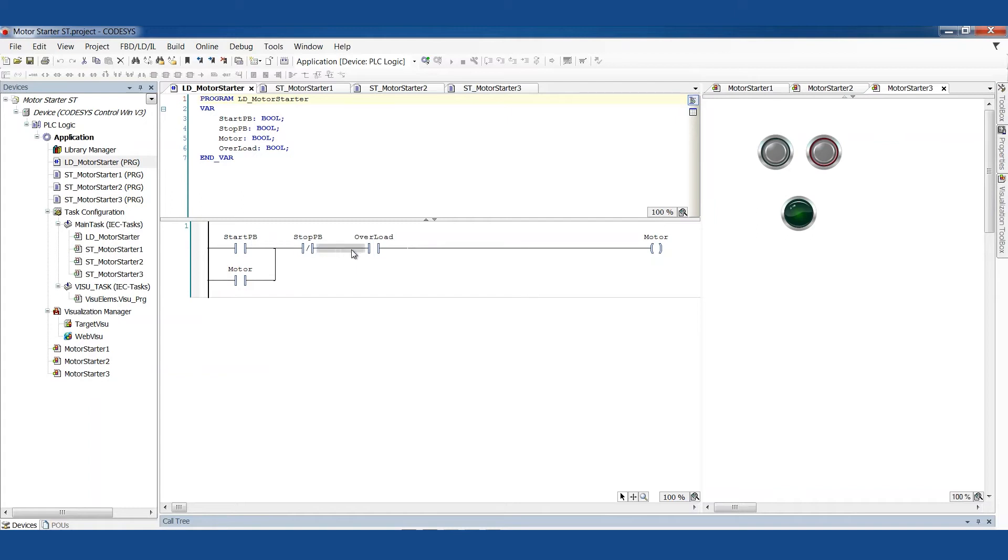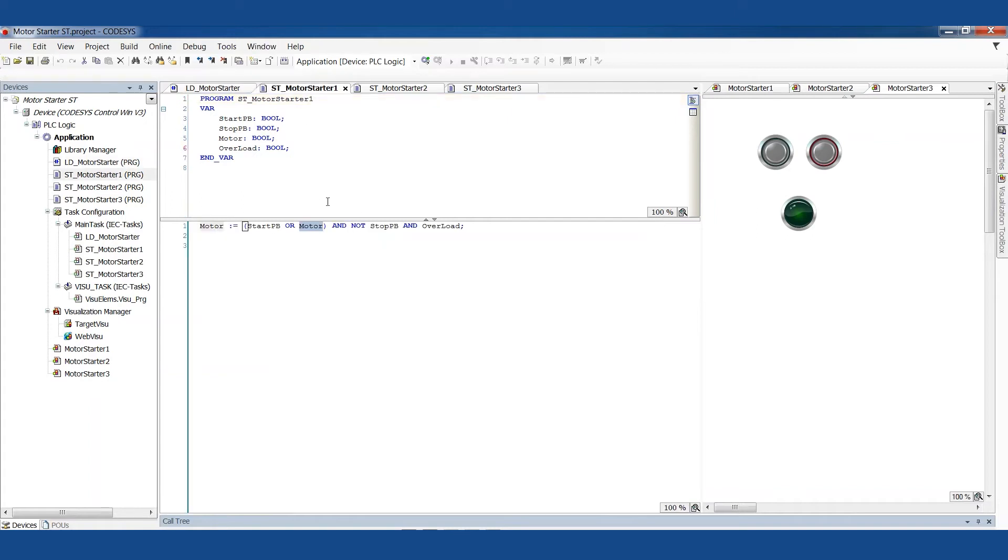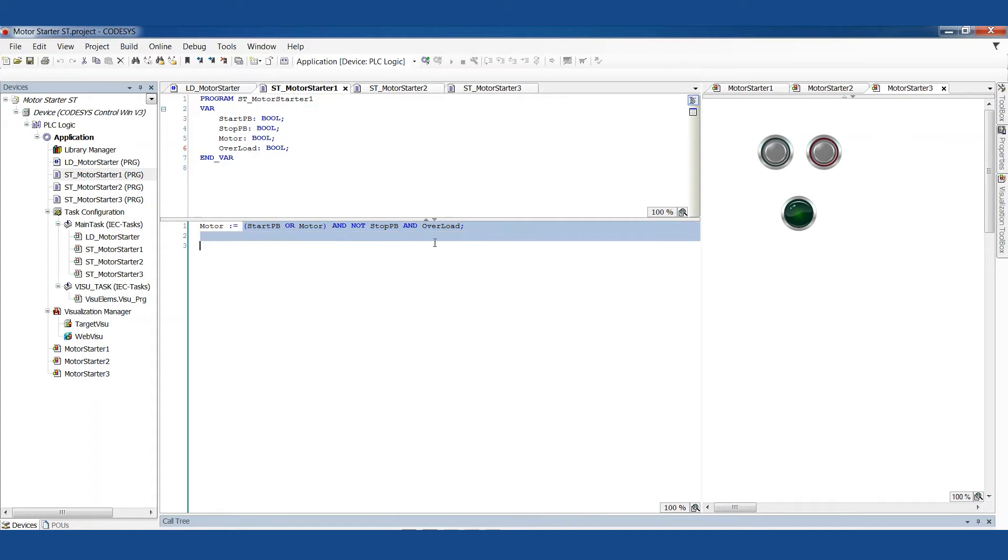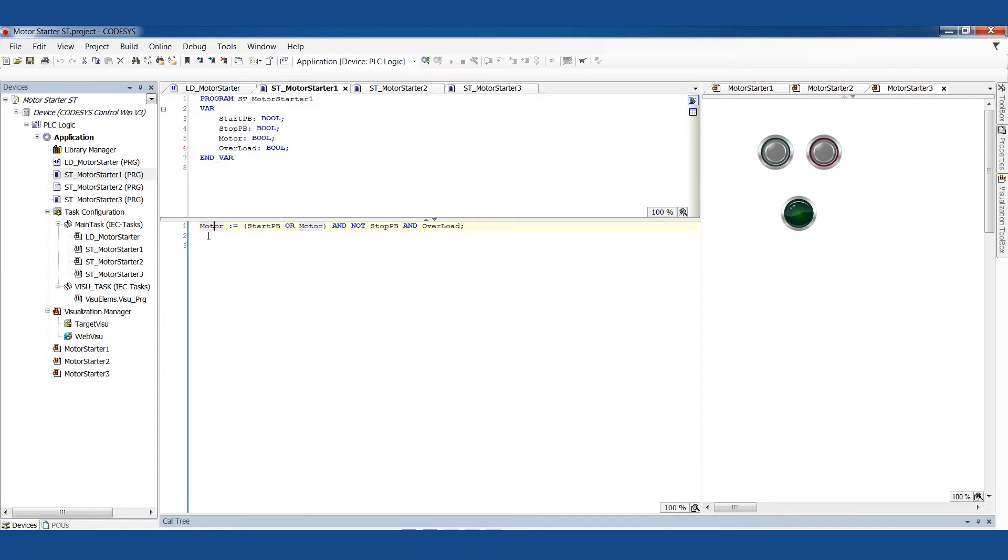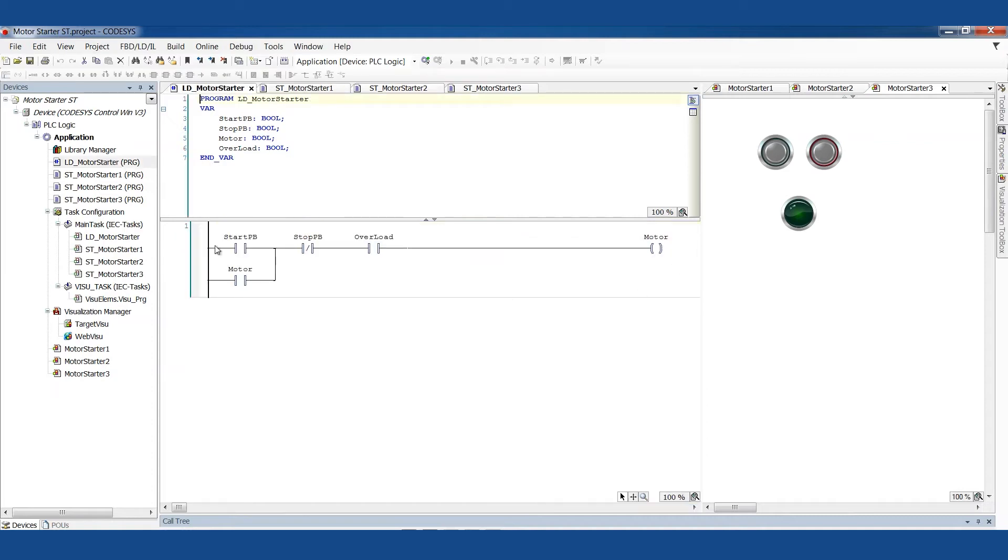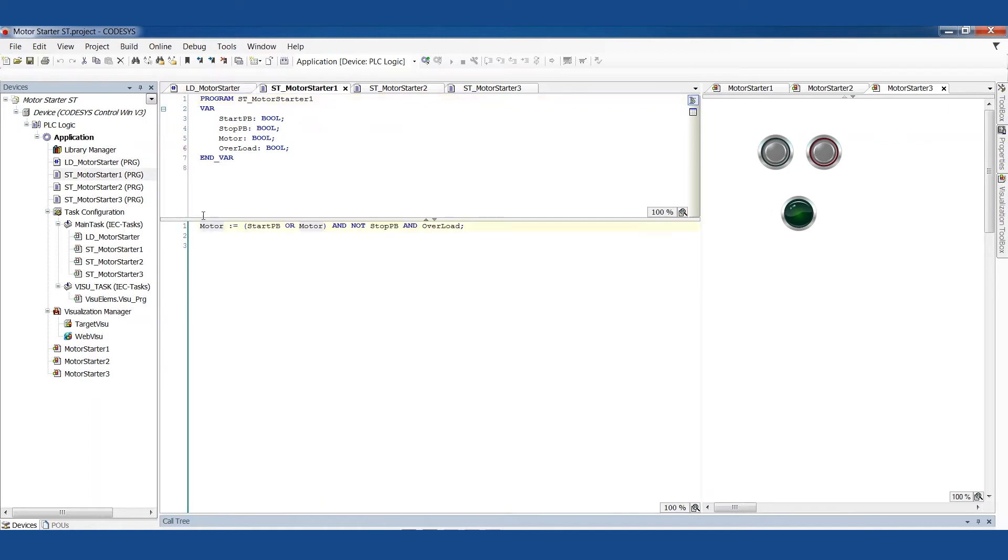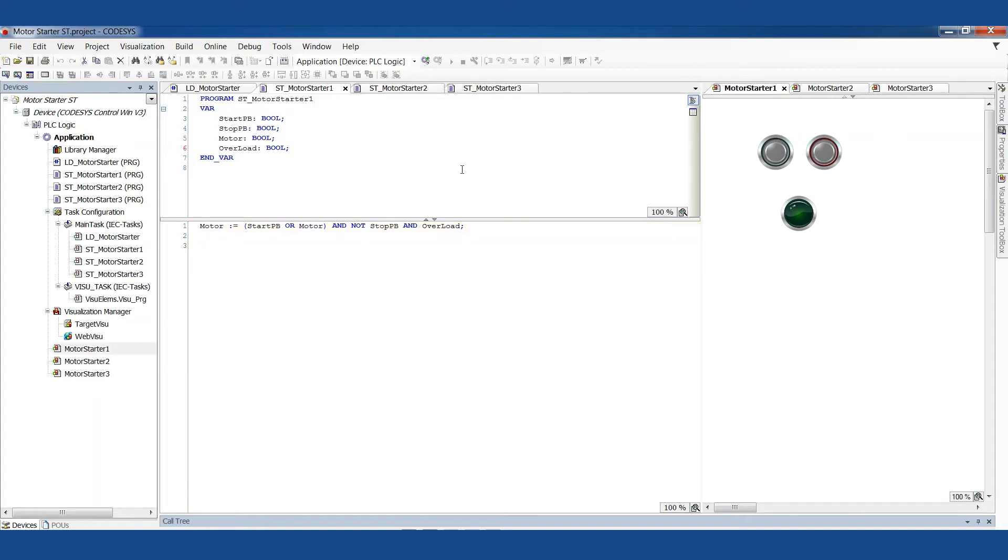The next thing we're looking at is not stop button and overload. And it's and because it's in line like this. And in structured text, this is the assignment operator. It means we take the result of the formula on the right and we put it into this variable here. So this is identical to the ladder logic, the Boolean logic. Same thought process, same approach.